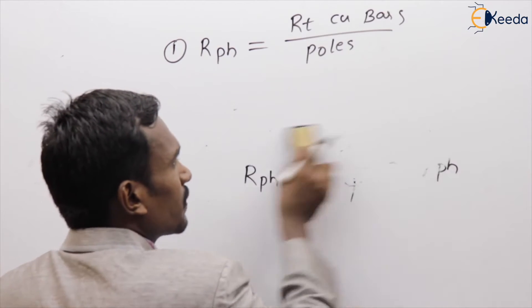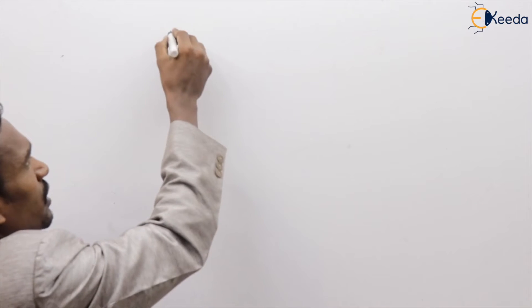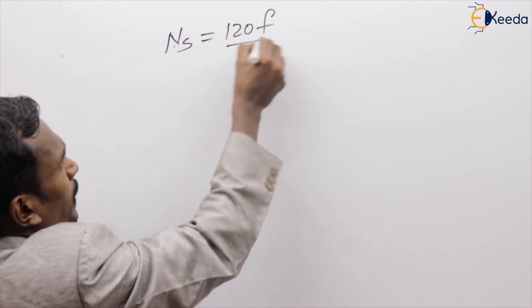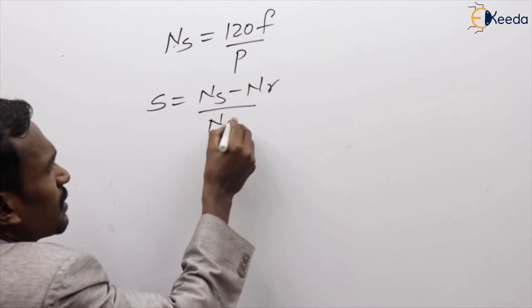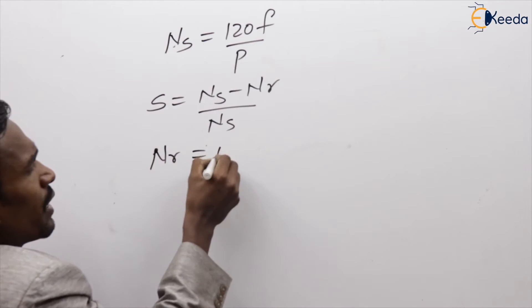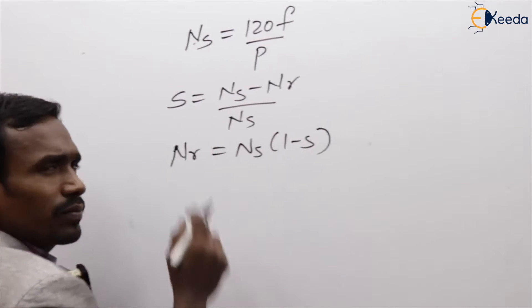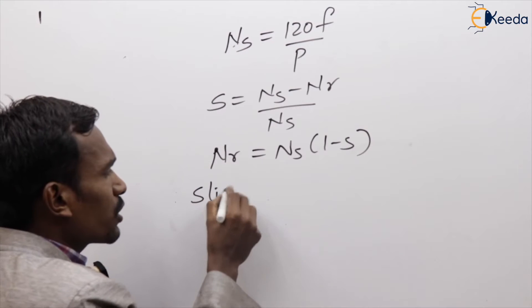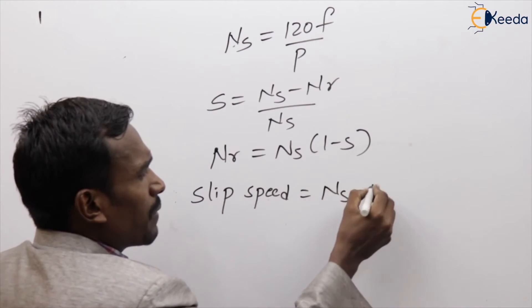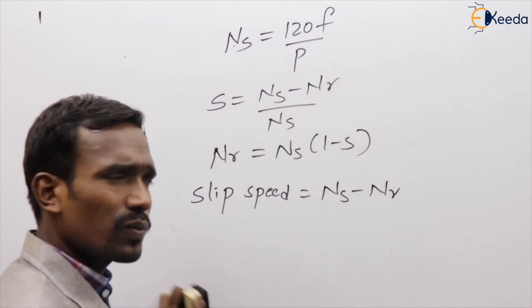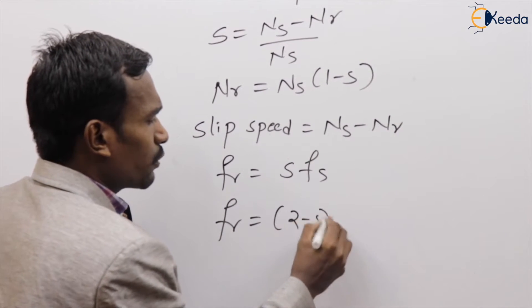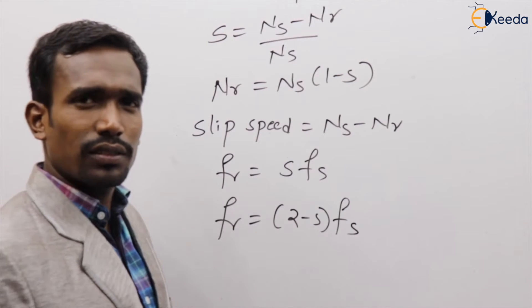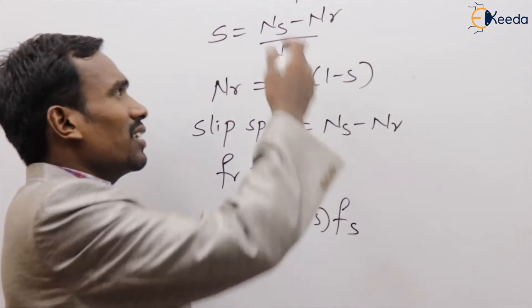Next, the second formula — speed equations. We have NS equals 120F by P, and S equals (NS minus NR) by NS, and NR equals NS into (1 minus S). Rotor frequency for positive sequence is S into Fs, and rotor frequency for negative sequence is (2 minus S) into Fs. These are the main speed equations.